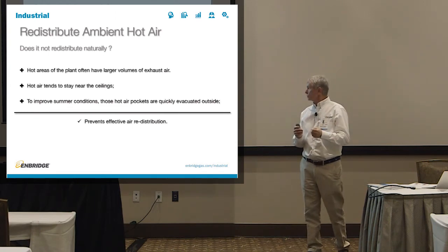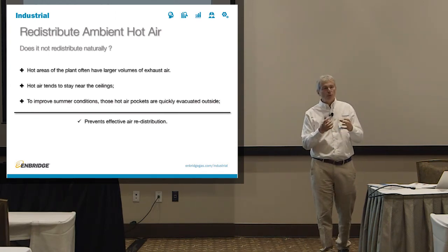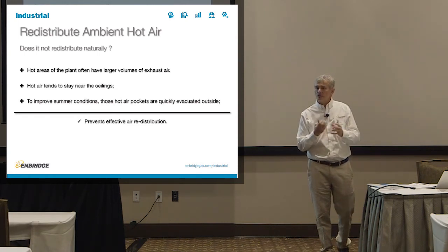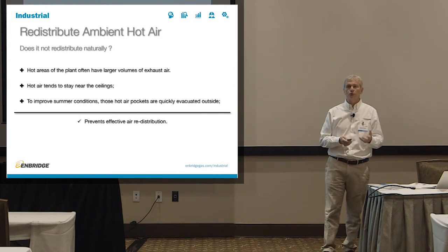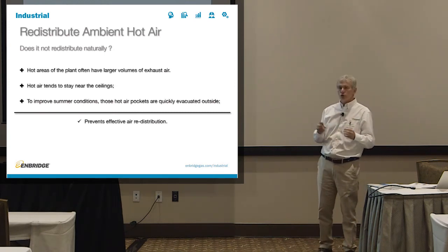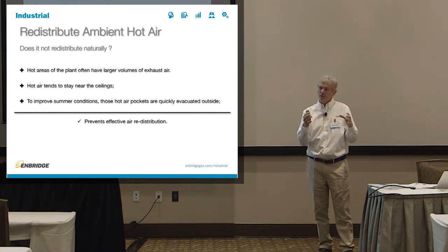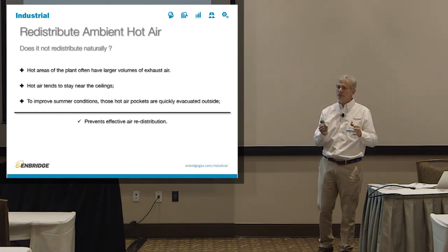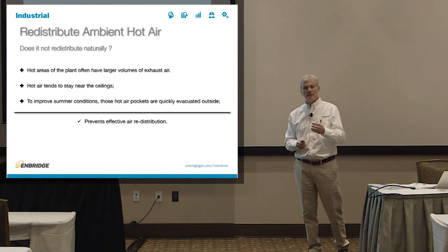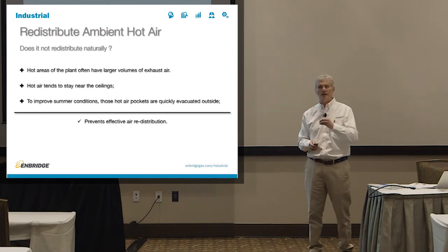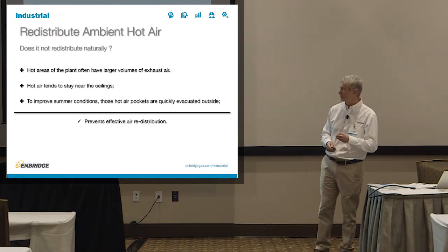So to improve summer conditions, as we said, all those hot pockets are quickly evacuated, so the heat doesn't have any opportunity to redistribute. Usually what happens is you have so much exhaust above the hot areas of the plant that you're pulling air not only from that side of the plant, but also through the shipping doors, through the shipping docks, wherever air can come in. And now you're generating a drafty environment for everybody else, so you would evacuate that hot air above the oven or extrusion equipment. That's very common. And that prevents that effective redistribution, so you have to have some way of mechanically distributing the air if you want to take advantage of this opportunity.